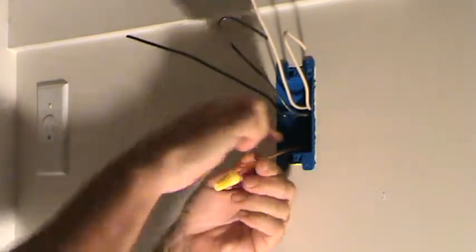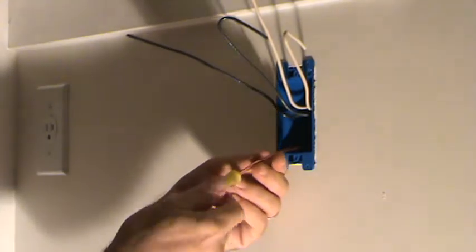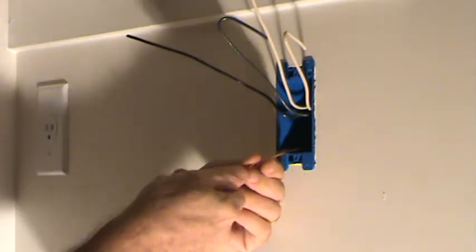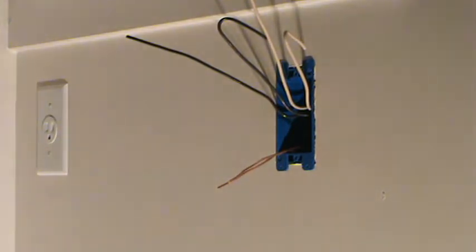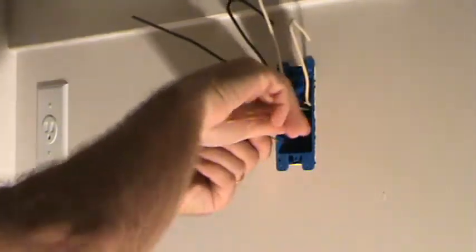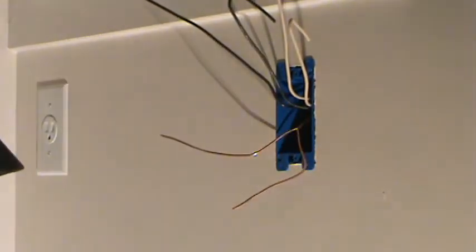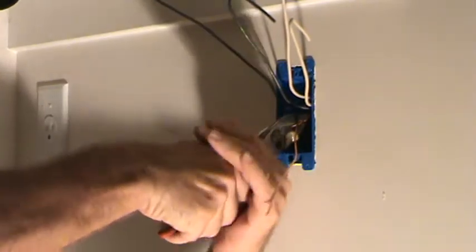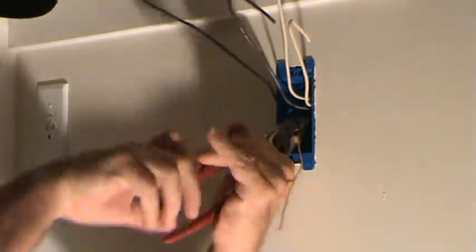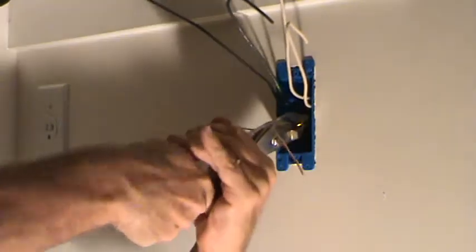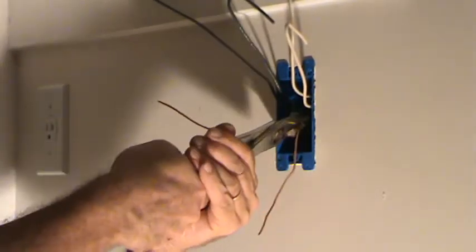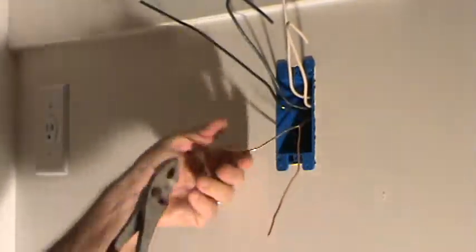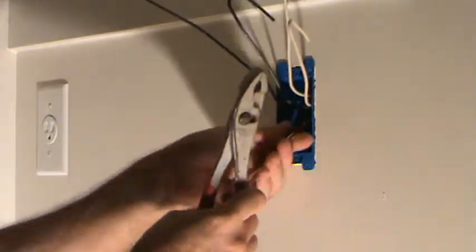Now, could I have connected those together and twisted them? Actually, let's do that. I'm going to twist these together first in the back. This is going to be my little insurance policy. In case the wire nut ever comes off, it's always important to have all your stuff grounded. So because we've got these ground wires in here, I don't want the wire nut coming off ever. So I just got a couple little twists in there.